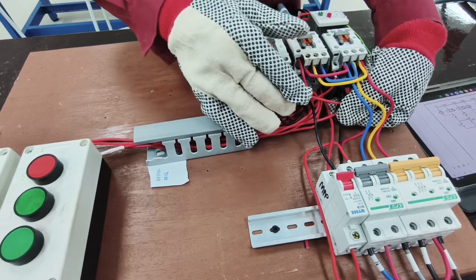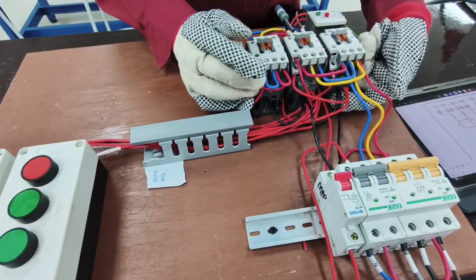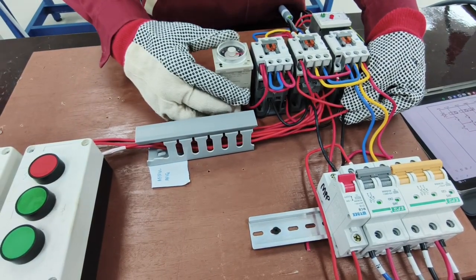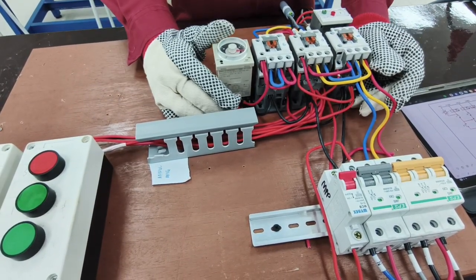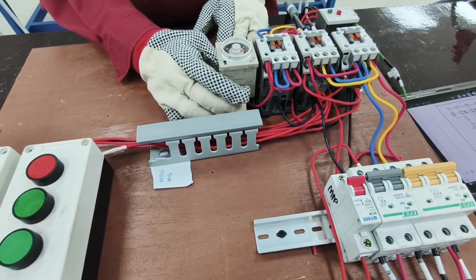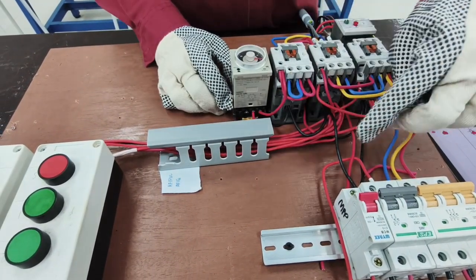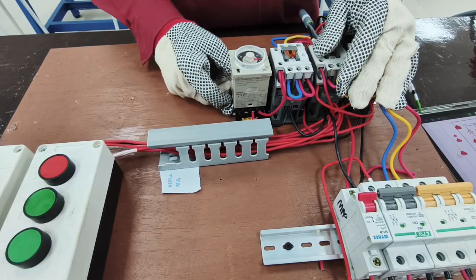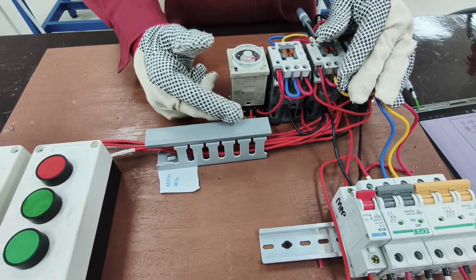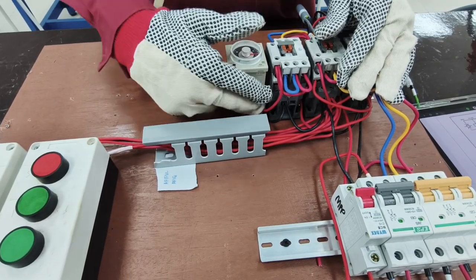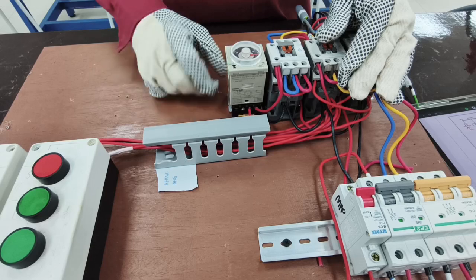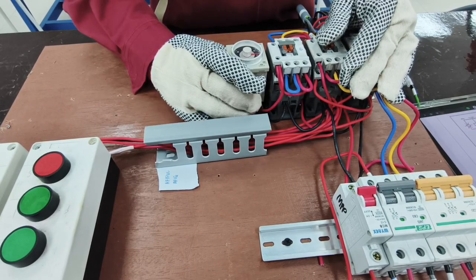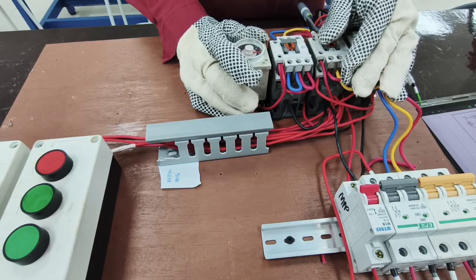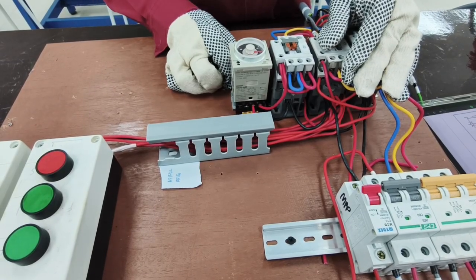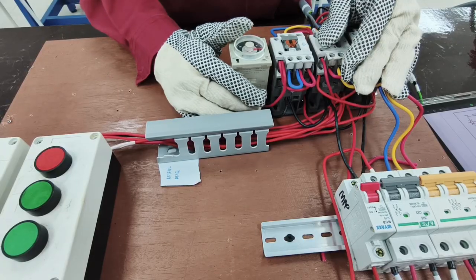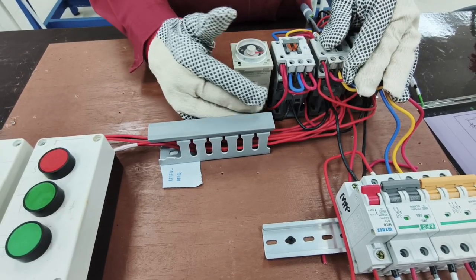Okay, then we also loop from the A contact to the timer, point number 7. The outgoing from the timer is point number 2. Then we go to the neutral. We also loop the same point to the common contact on the timer, which is point number 8. This timer also has normally closed and normally open contacts: normally closed is point number 5, and normally open is point number 6.